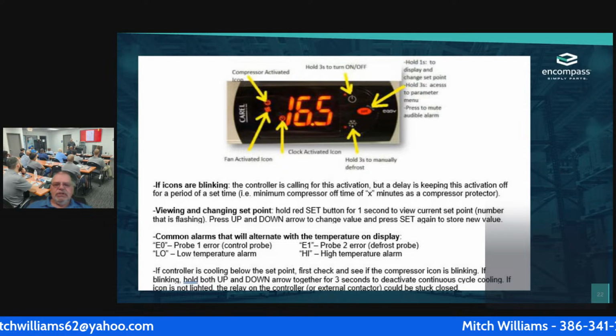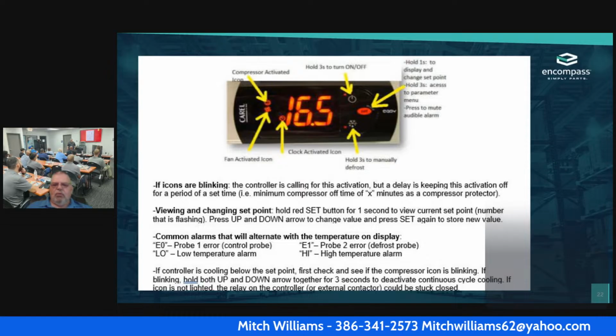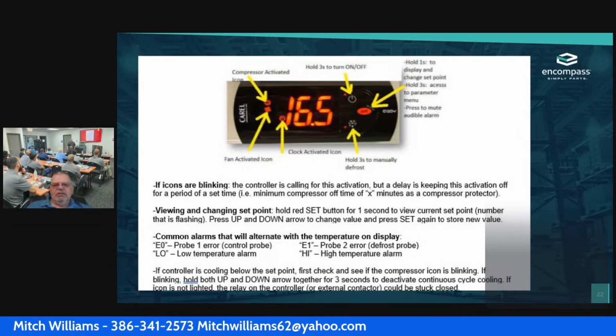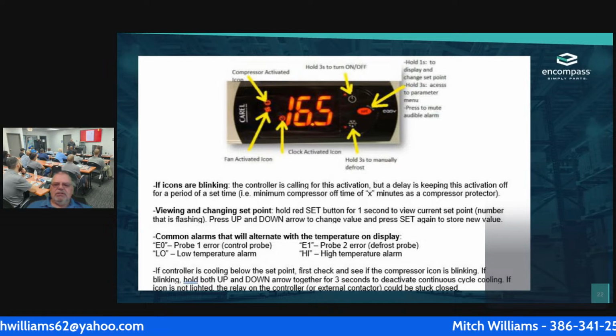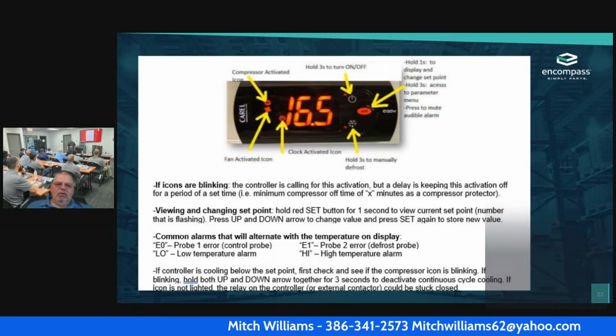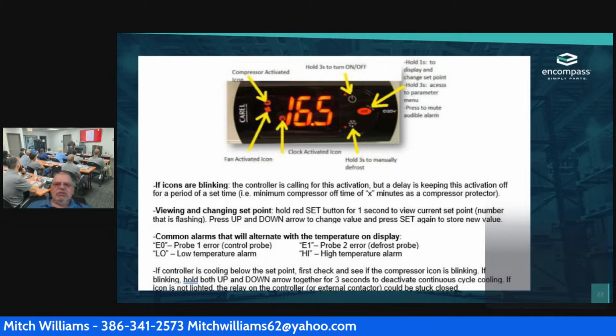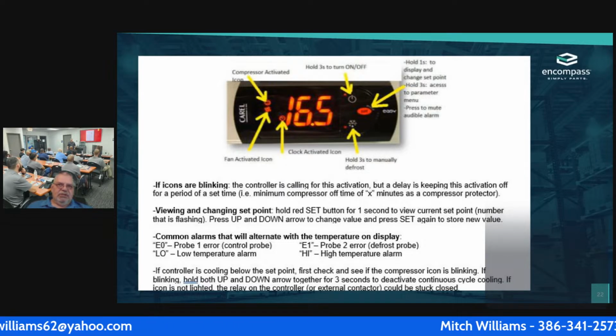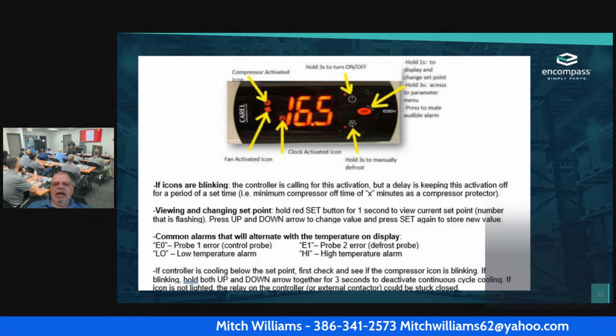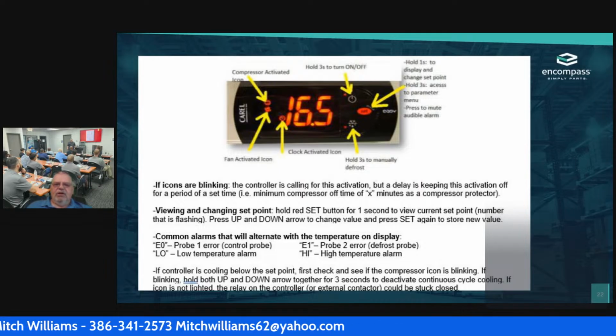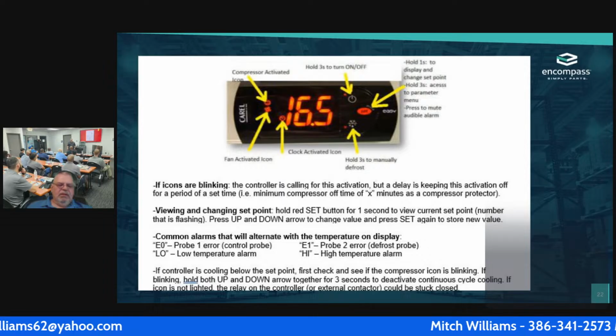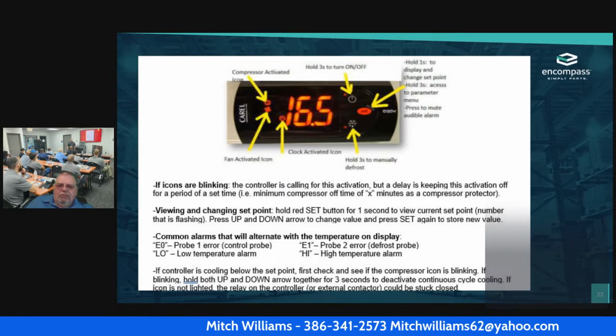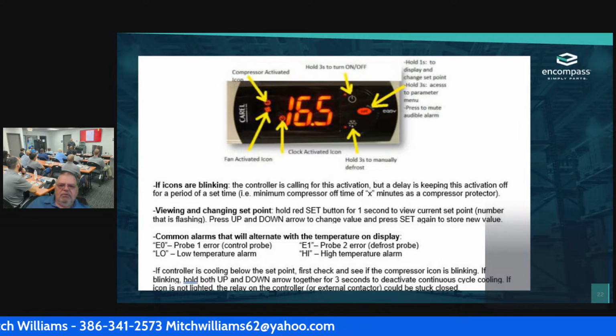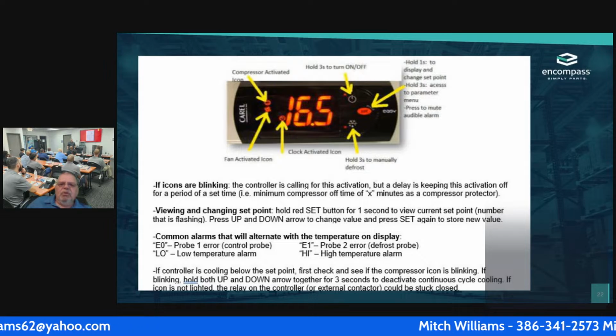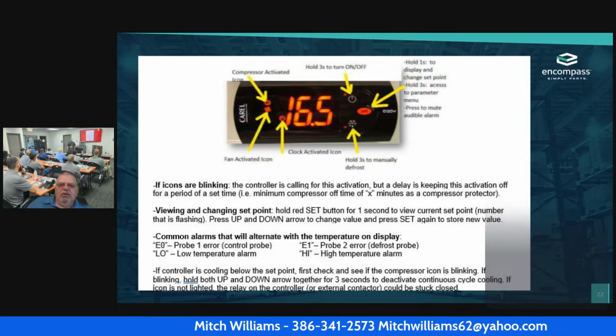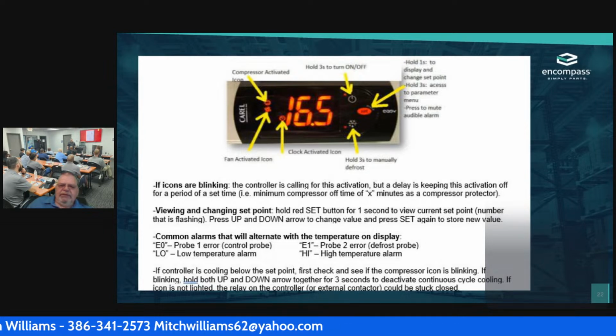Okay, viewing and changing the set points. I can hold that red set button on the far right side for 1 second. That views the current set point. That tells me what temperature it's at. I press the up and down arrow to change the value and press set again to store the value. So if you see this one is 16.5, that tells me right there that it's in Celsius, not in Fahrenheit. So I can go and change that from Celsius to Fahrenheit. That will give me the Fahrenheit temperature. Excuse me. Then once I do all that, changing the set point, I just move it with the up and down to either increase or decrease that temperature.